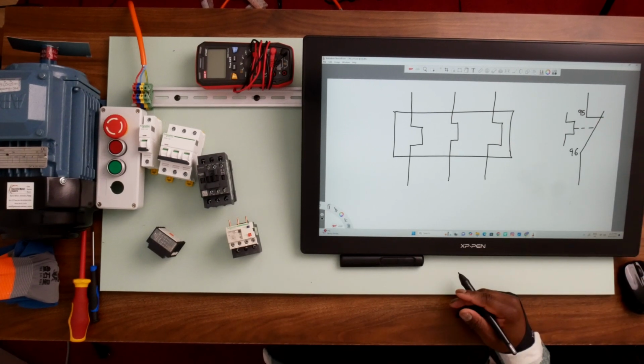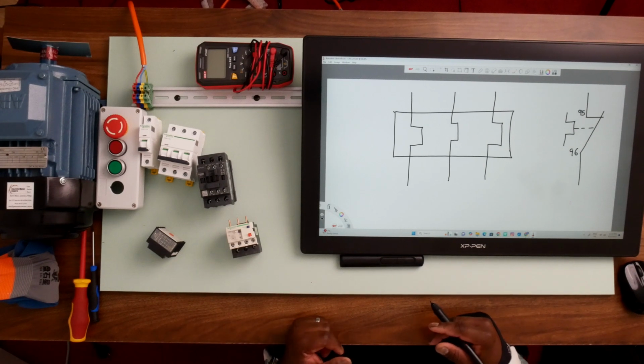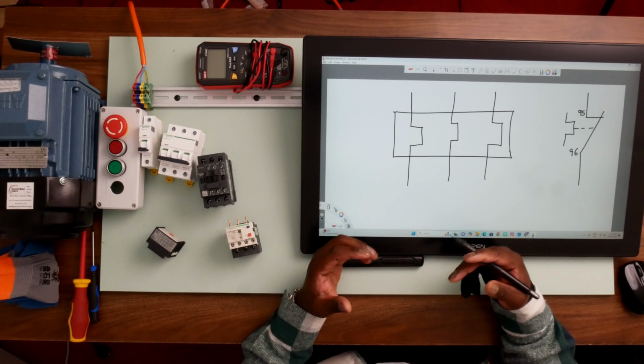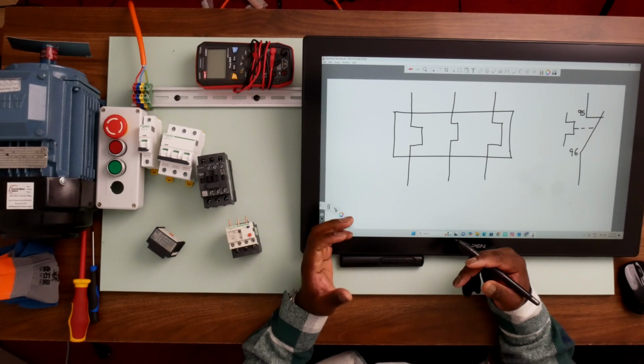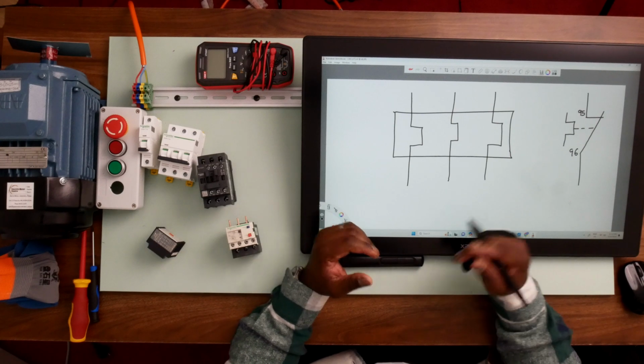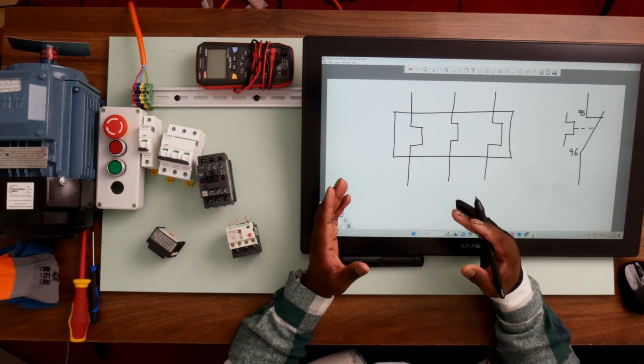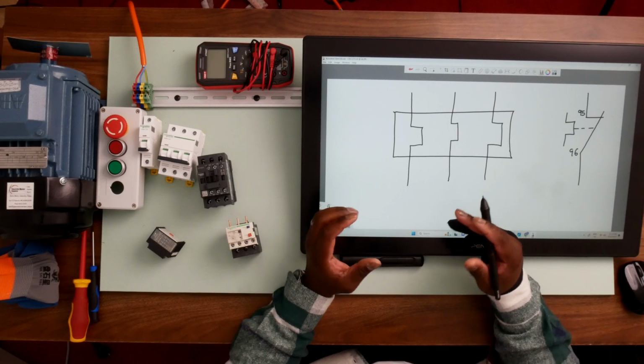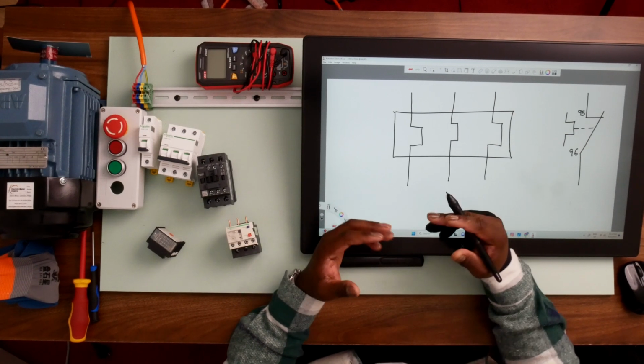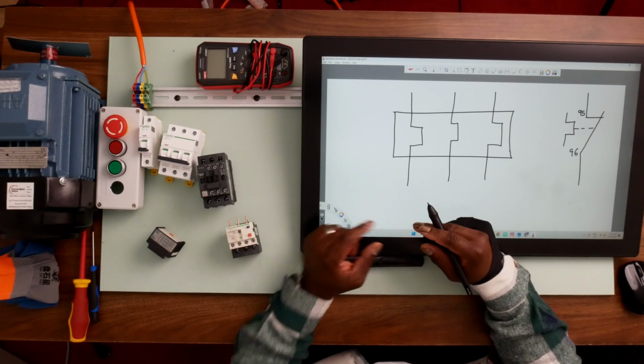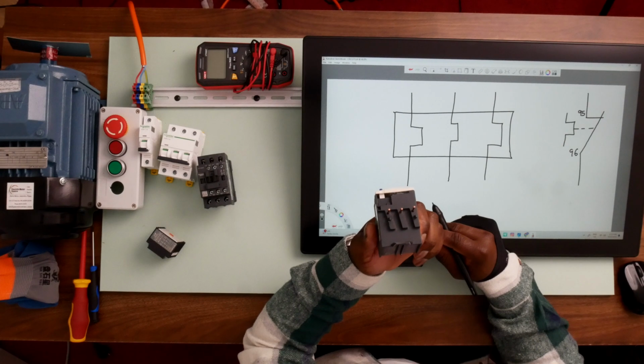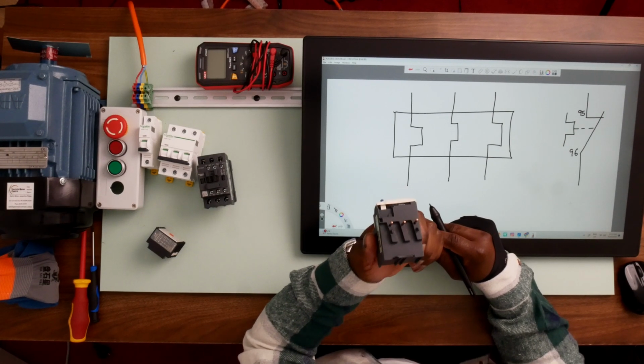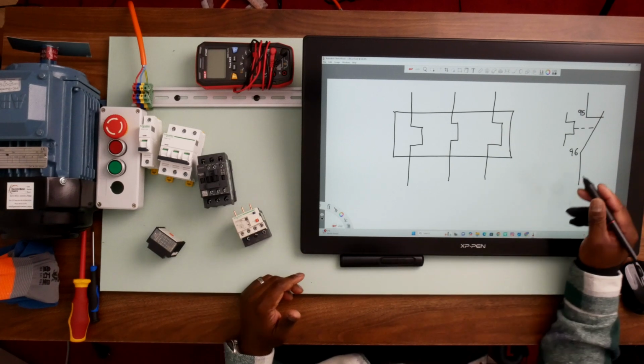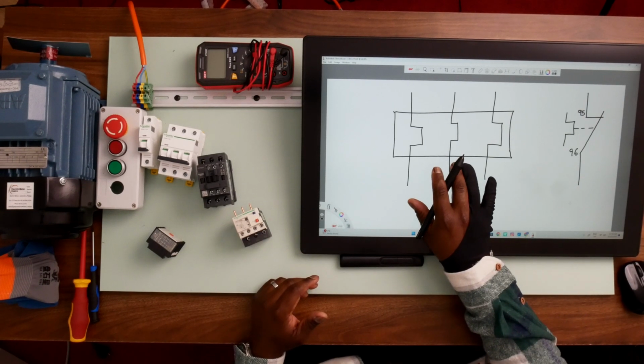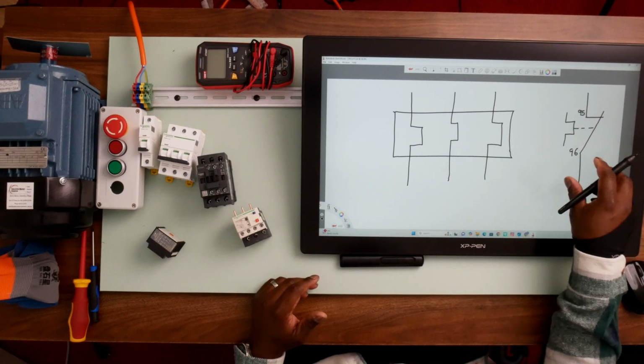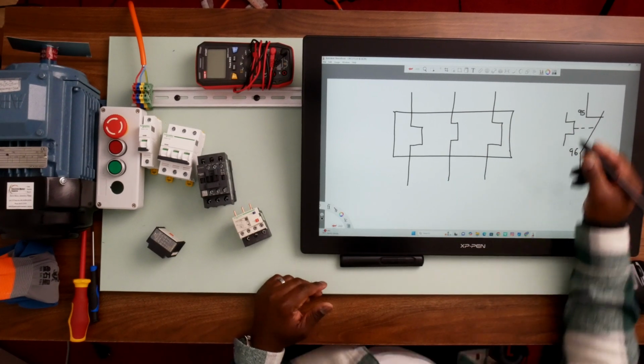As we mentioned earlier on when we discussed normally open and normally closed contacts, an overload relay is an exception which doesn't follow the common labeling rules that we use for normally open and normally closed contacts. So the normally closed contact on an overload relay is labeled 95 and 96. It doesn't follow the rule of 1 and 2, or of numbers that end in 1 and 2. So always bear in mind that for this old school type of overload relay, you're more likely to find the normally closed contact labeled as 95 and 96, just like what we've done here. So this is the power circuit symbol for an overload relay, and this is the control circuit symbol for an overload relay. Now let's move on to the next component.